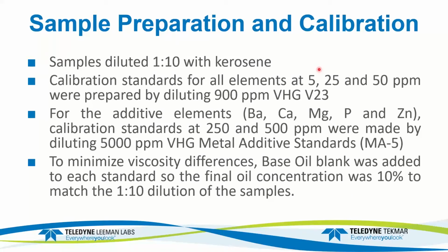We said earlier, all the samples are going to be diluted 1 to 10 with kerosene. We prepare calibration standards for all the elements at 5, 25, and 50 ppm by diluting 900 ppm VHG V23, which is a product from LGC Standards. Additive elements can be present at much higher concentration, so there's a separate metal additive standard, MA-5, that we use to calibrate up to 250 and 500 ppm. To minimize any viscosity differences, we use blank oil in each standard so that the final oil concentration is 10%, which matches the 1 to 10 dilution of the samples.